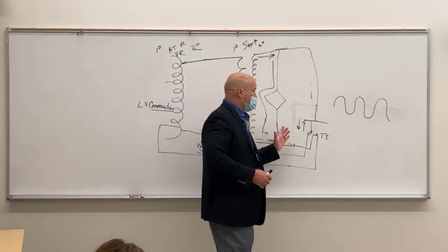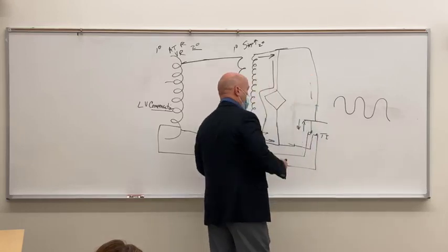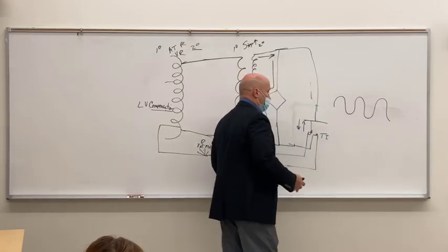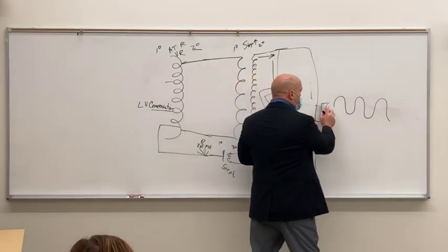Dental units don't use enough kVp to get that reverse voltage. So the x-ray tube actually becomes the rectifier bank.